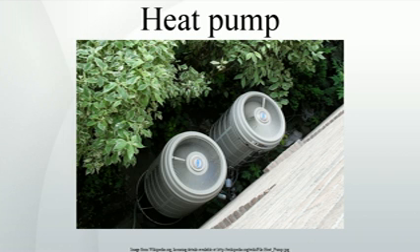The low-pressure liquid refrigerant then enters another heat exchanger, the evaporator, in which the fluid absorbs heat and boils. The refrigerant then returns to the compressor and the cycle is repeated. It is essential that the refrigerant reaches a sufficiently high temperature, when compressed, to release heat through the hot heat exchanger, the condenser. Similarly, the fluid must reach a sufficiently low temperature when allowed to expand, or else heat cannot flow from the ambient cold region into the fluid in the cold heat exchanger, the evaporator.